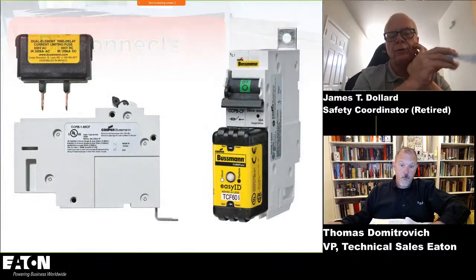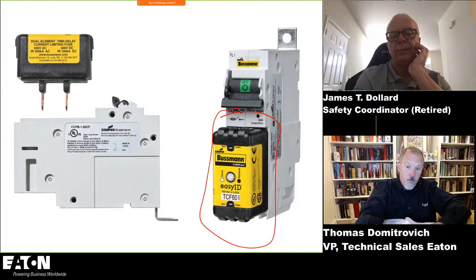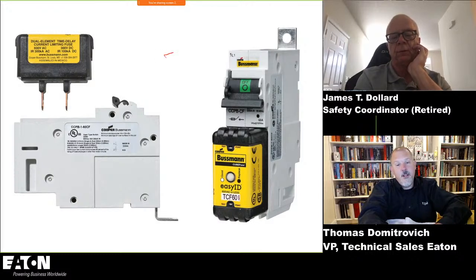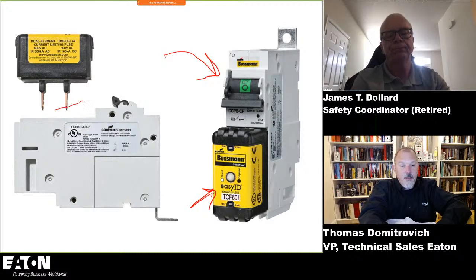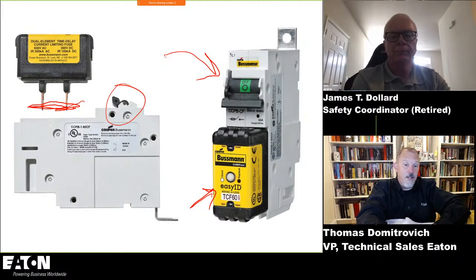And the way those cubes are made and listed, you can't pull the cube fuse out while the device is in the closed position. A lot of people miss that. This here is just a UL 98 switch, and the yellow thing is your fuse. There's a pin that goes through these leads when you turn this on, and you can't pull it out and you can't put it in while this is on. So that's a really nice way from a lockout tagout perspective. You pull that fuse out, and there's no way anybody can re-energize that circuit without that fuse in there. That's a good example of the hierarchy of risk control, your engineering controls.